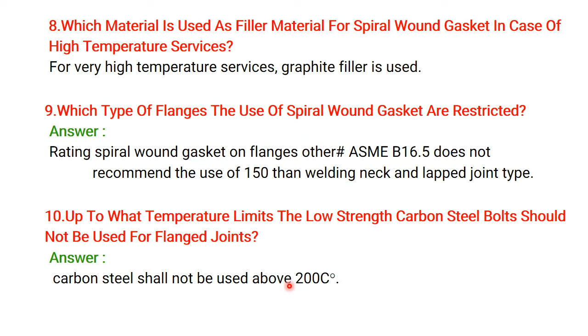On which type of flange is the use of spiral wound gasket restricted? Rating spiral wound gasket on flanges other than ASME B16.5 is not recommended, and then use on 150 weld neck and lap joint type. Next, up to what temperature limit should low strength carbon steel bolts not be used for flange joints? Carbon steel shall not be used above 200 degrees.